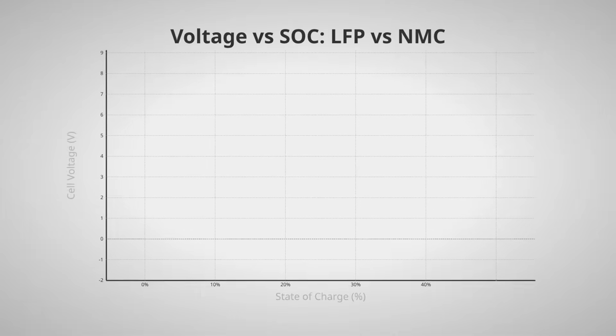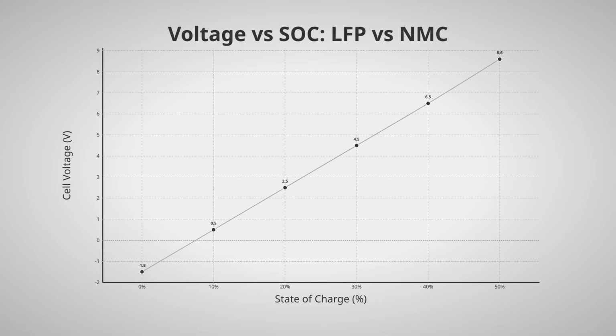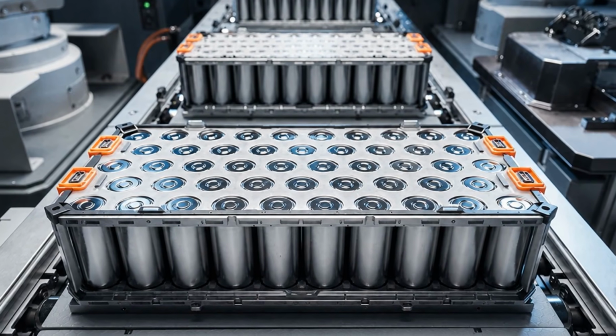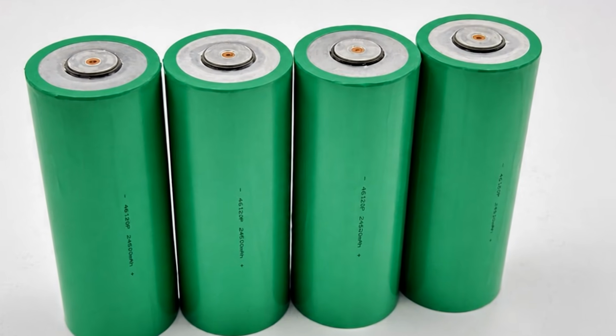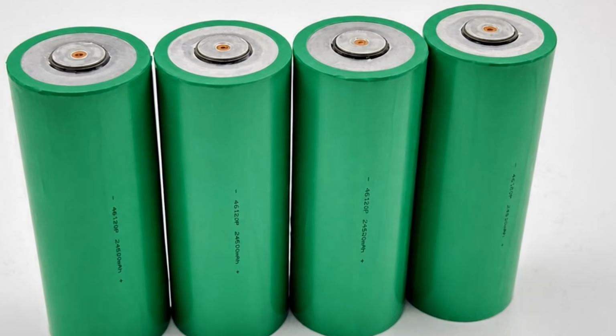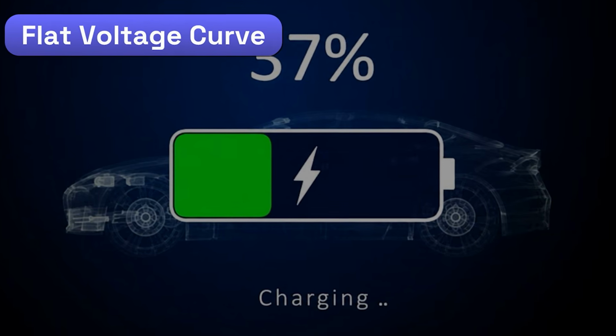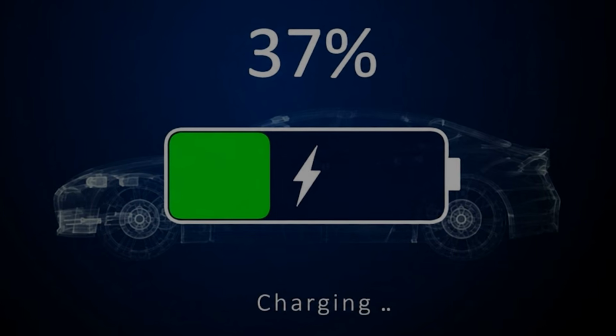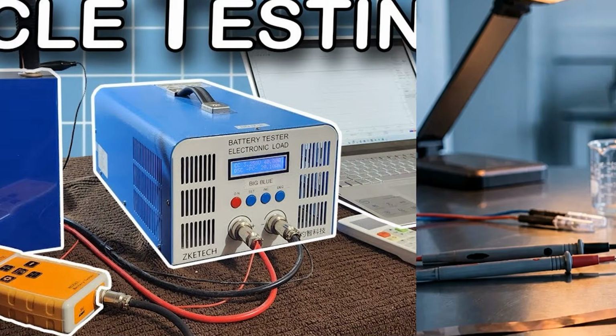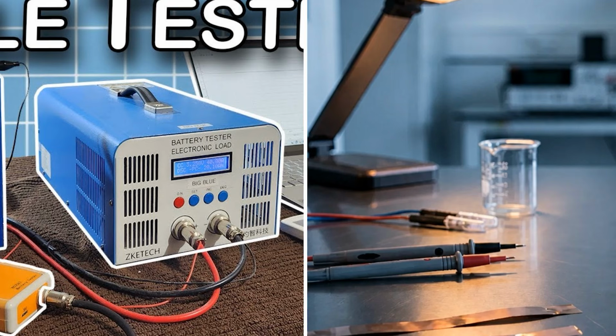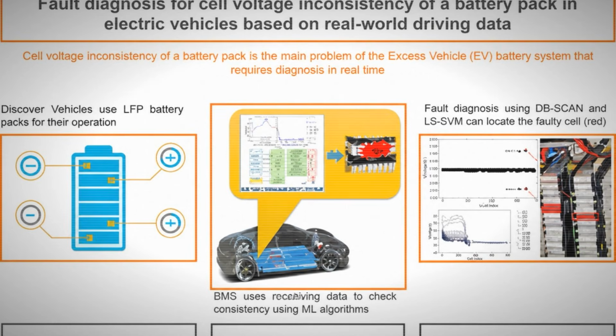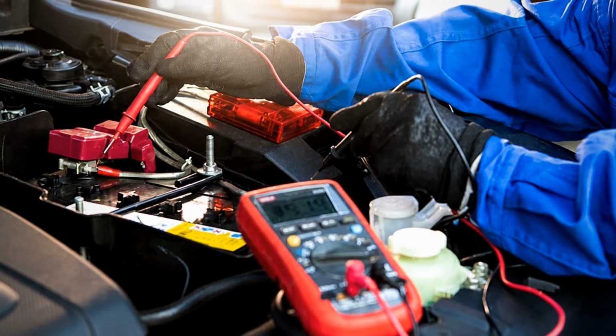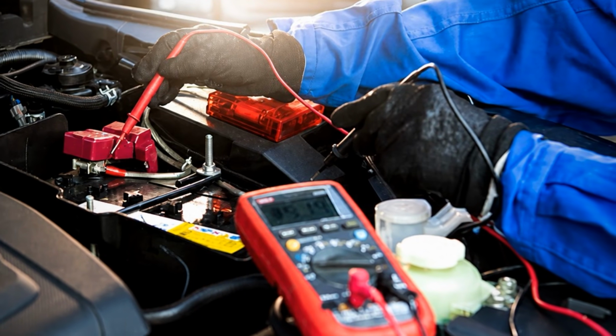Start with why LFP chemistry is fundamentally different from NMC at the voltage level, because this is the root of everything else. LFP batteries have a very flat voltage curve. What that means in practice is that between roughly 20% and 90% state of charge, the voltage barely changes. On an NMC battery, the voltage rises and falls in a way that allows the battery management system to accurately estimate remaining capacity at almost any point in the charge cycle.